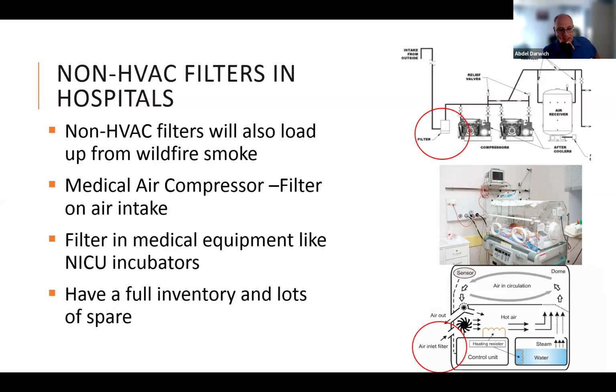What they noticed is that filter was clogging very, very quickly, and some hospitals actually lost their medical air. So now we recommend having 2 filters in parallel, so that if one clogs you can switch to the other. We also ask hospital owners to keep an inventory of those filters in stock, so they can be changed frequently.